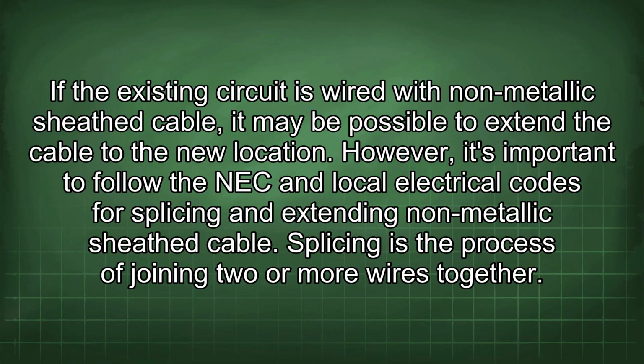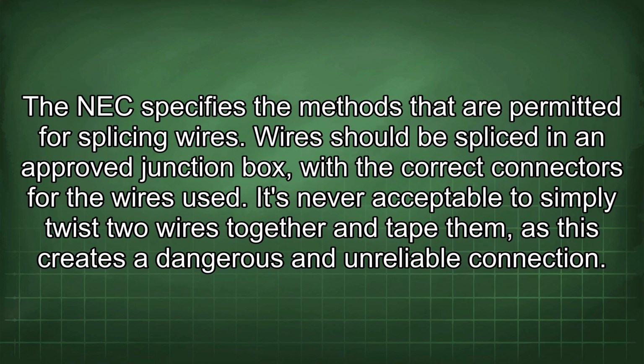Splicing is the process of joining two or more wires together. The NEC specifies the methods that are permitted for splicing wires. Wires should be spliced in an approved junction box, with the correct connectors for the wires used. It's never acceptable to simply twist two wires together and tape them, as this creates a dangerous and unreliable connection.